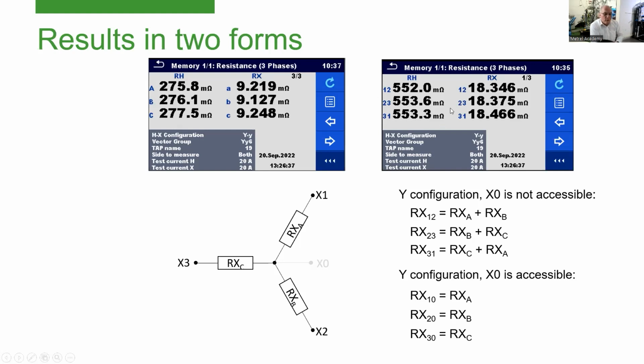Sometimes in the past, I got many questions that the results measured by one instrument, the DTA for example, compared to some other manufacturer are completely different. But the difference was only because of this. The other instruments showed only the resistance between terminals, and in the DTA we showed only the resistance of the winding. Now, on these instruments, you have both possibilities. So if you want to compare with the others, you use this one. If you want to have these results, you take this one. This is, I think, the answer to the question.